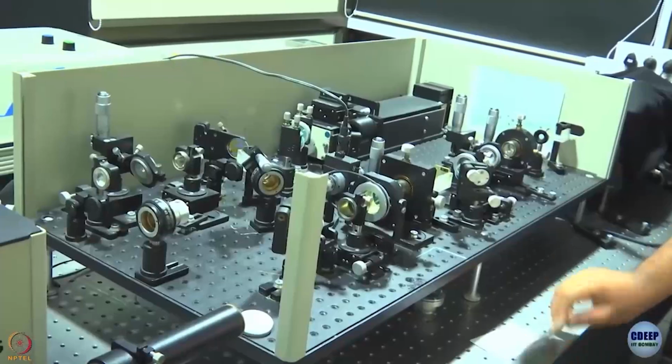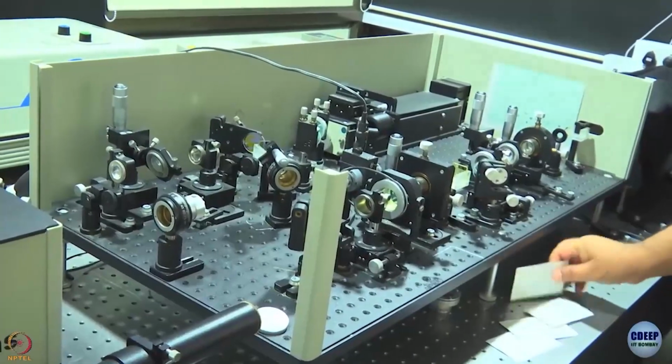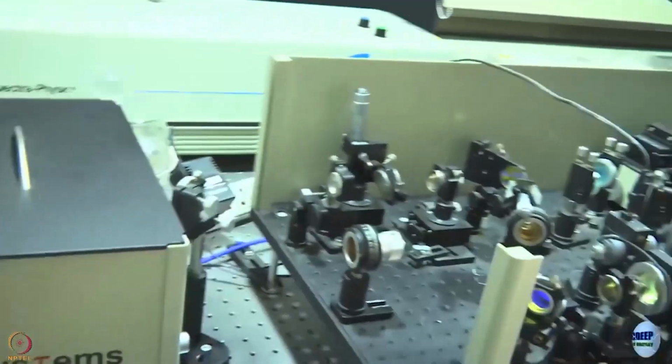Okay. Right. This here is the optical unit. Remember where laser light is supposed to come from? It is supposed to come from this direction. Now, let me show you the red light if you can see it. You see that red spot of light? That is the output of the titanium sapphire laser. To your eye, it seems that it is a light that is always on, but actually it is not. We have hundreds of femtosecond pulses there, and the pulses are coming at a repetition rate of 76 megahertz, too fast for our eyes to make out the pulses from each other. That is why it looks like continuous wave.